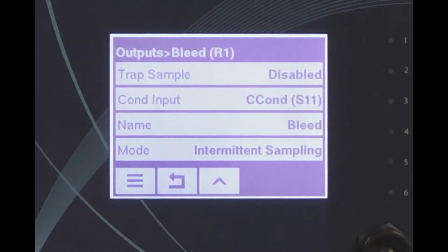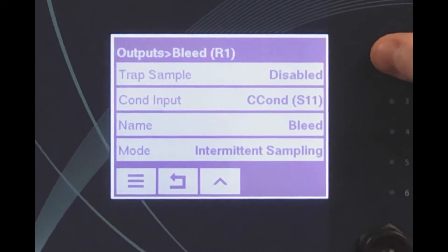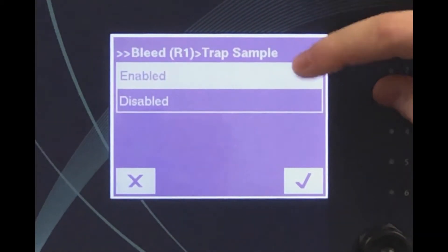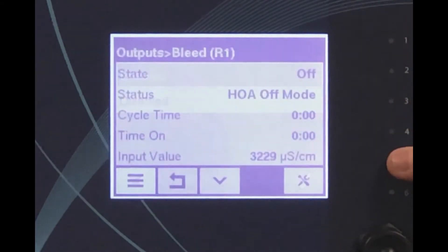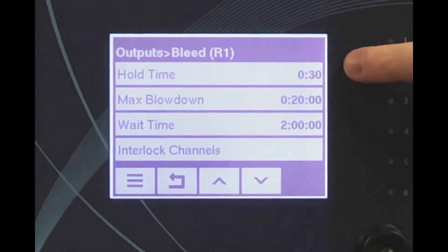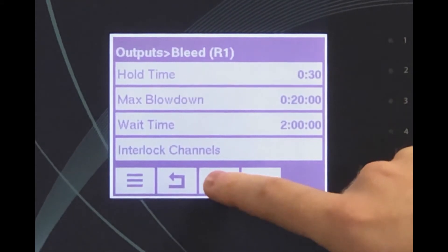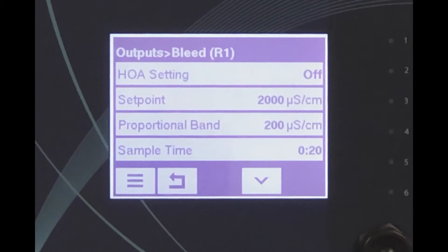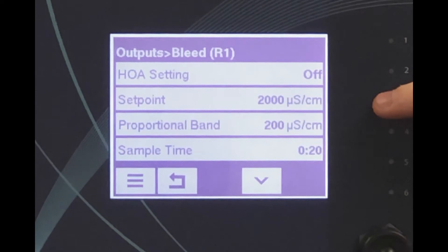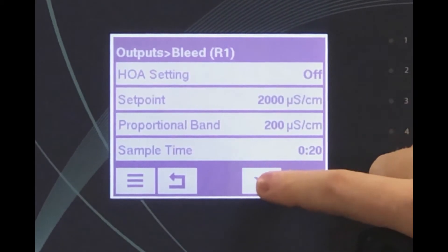The best control of a boiler is usually done with an intermittent sample that is trapped for a short period of time to allow any flashing to condense. The trap time is called the hold time. In addition to trapping the sample, an improved method of control calculates the blowdown time based on how much over the set point the boiler conductivity is at the end of the hold time. This is done using the proportional band and the max blowdown time settings.